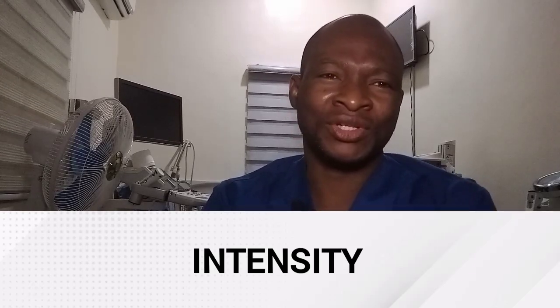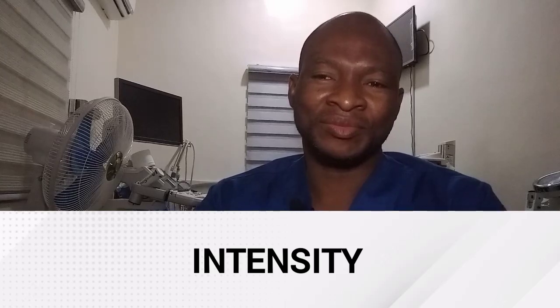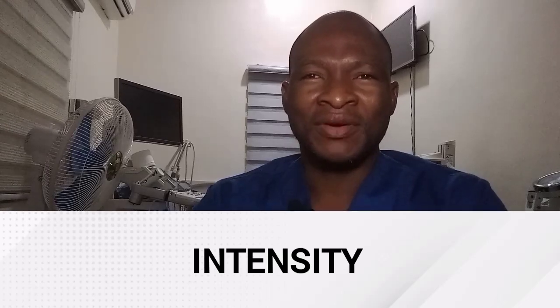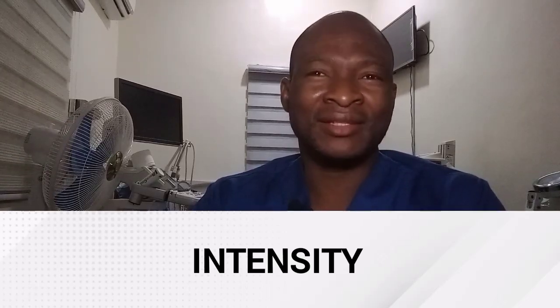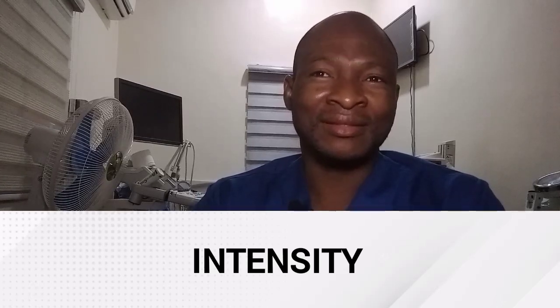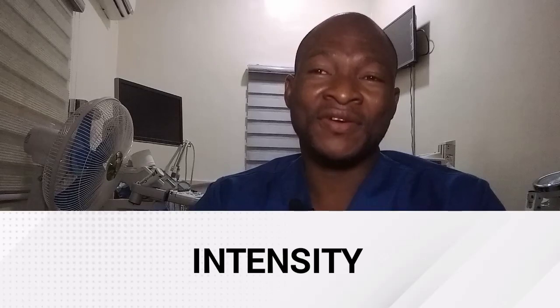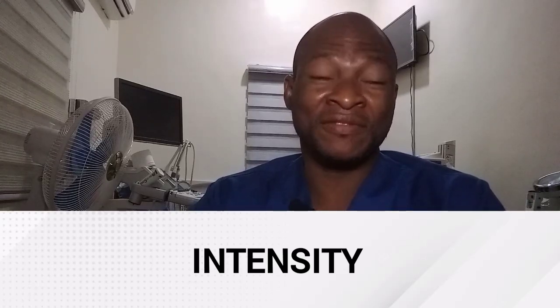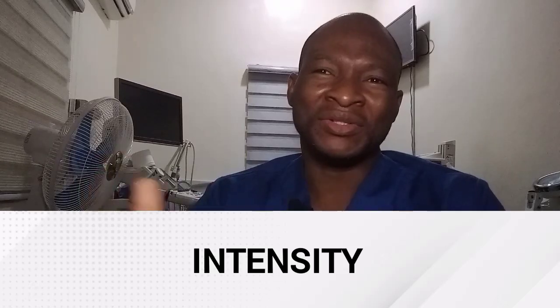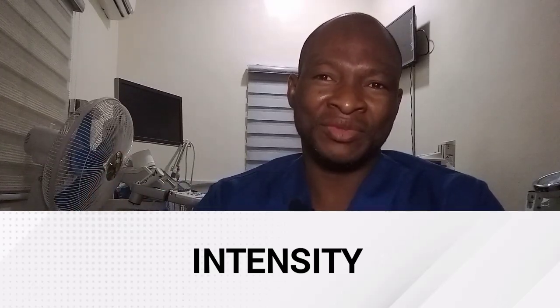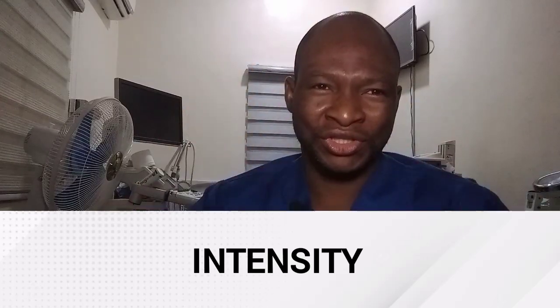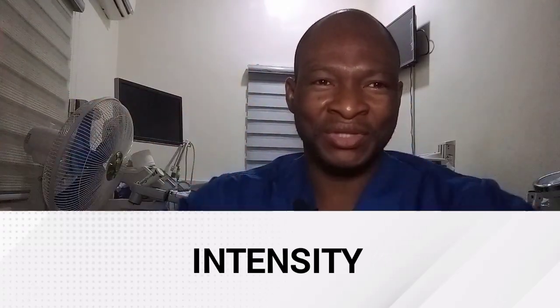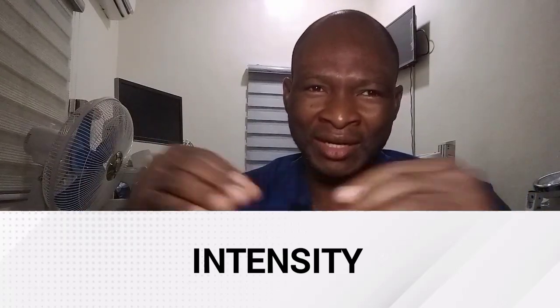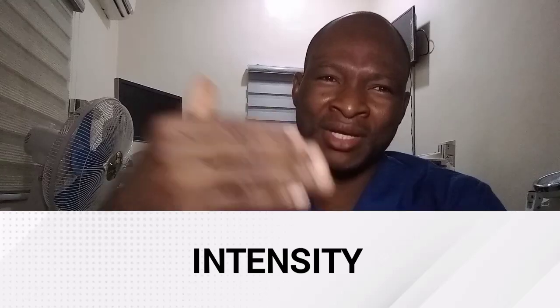The higher intensity generates stronger echo, which improves system sensitivity. And of course, intensity in the equation is power measured in milliwatts divided by beam area in centimeter squared. However, the possibility of biological effect is also increased with higher intensity. The intensity of the diagnostic ultrasound beam is difficult to measure because it varies considerably within the beam. The beam profile is an hourglass shape because sound converges then diverges. So after the focal point, there is divergence. So how do you measure across these various beam widths?